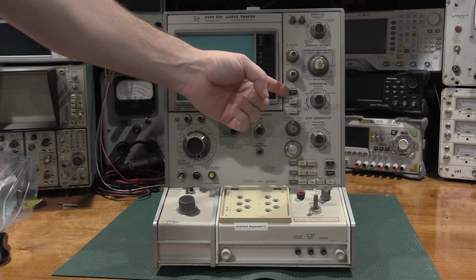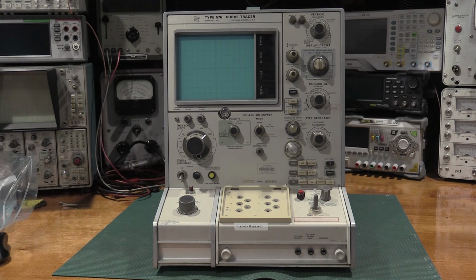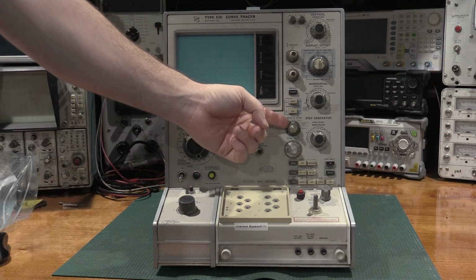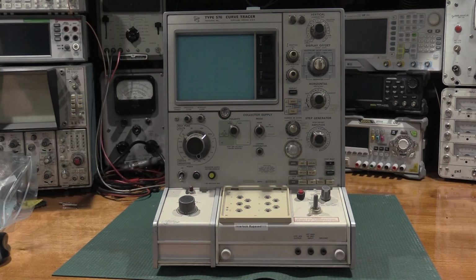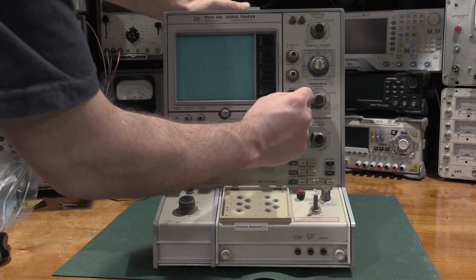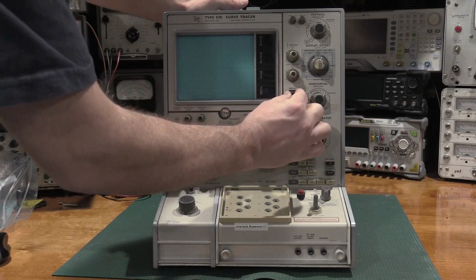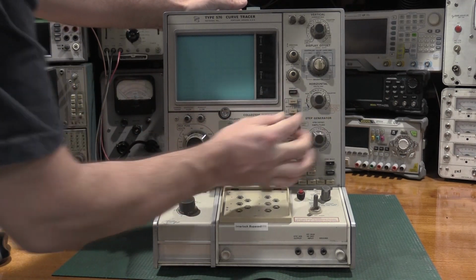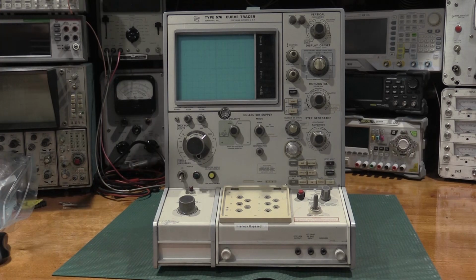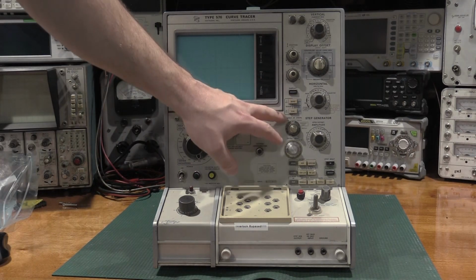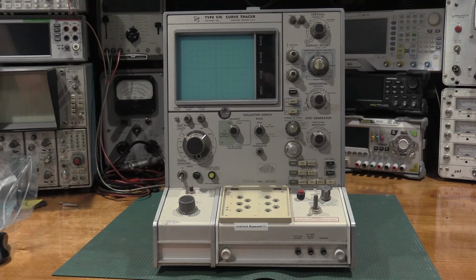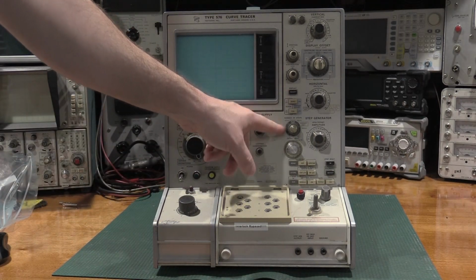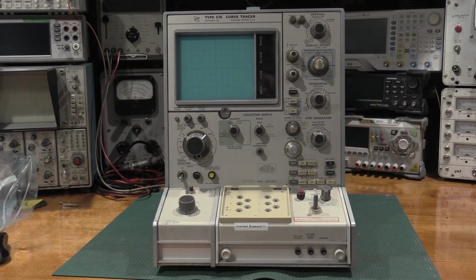The other thing is this switch pack is in the drive line for the CRT. These switches are very known for getting dirty. They will cause lots of noise. One of the tests there is to grab the invert button and just wiggle it like this. And if the display is going nuts, that's a dirty switch. Don't worry about it. These just need some cleaning and servicing. Everyone I know that has a 576, these 3 switches need cleaning and servicing. So that's been in every unit.